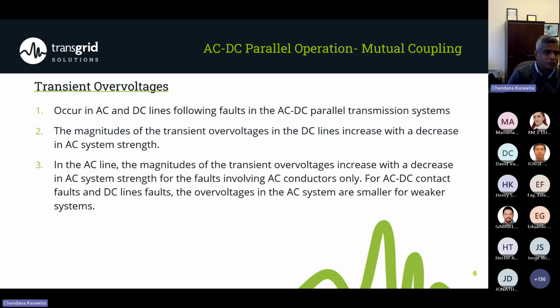The second issue is transient overvoltages. Again, transient overvoltages can happen both ways. When we have an AC fault, the DC line will observe some transient overvoltages. Similarly, when you have a DC fault, the AC line also can observe some transient overvoltages.